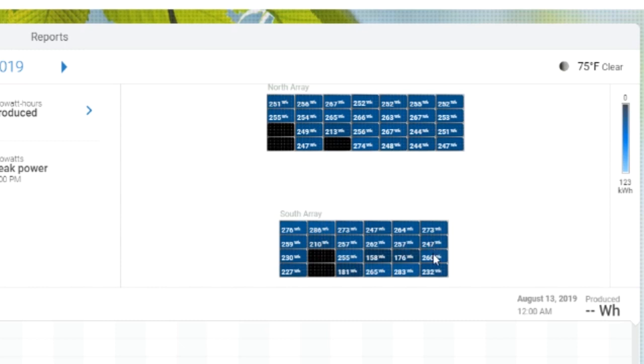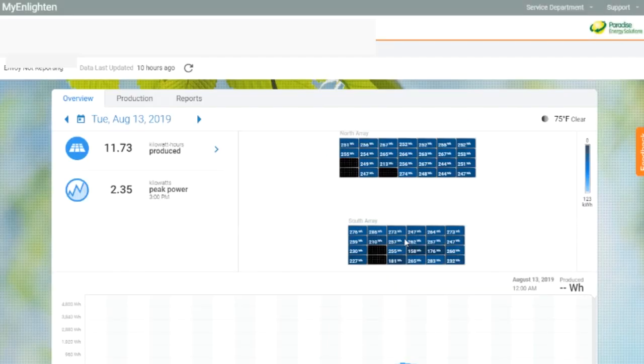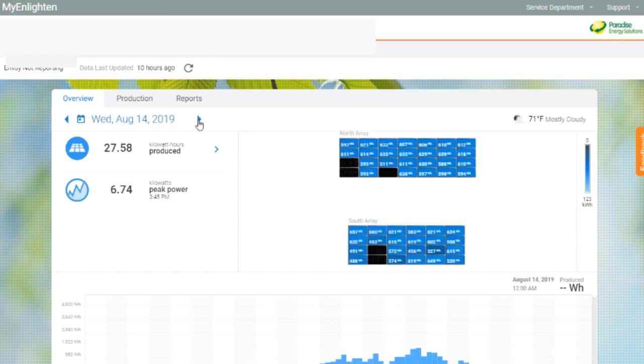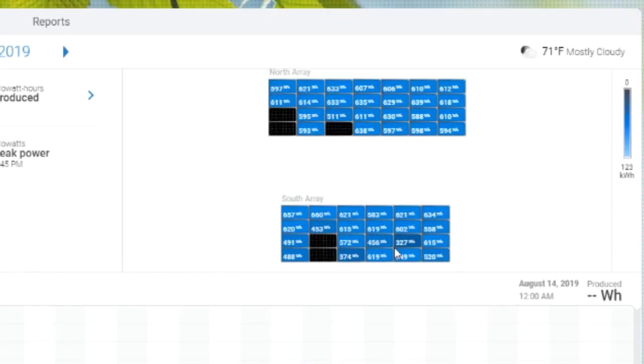So there's a pretty big difference in the amount of production. That tells me that these inverters are probably starting to fail. Let's jump around a few days. This is back on August 13th. Let's jump up to the next day, August 14th. And we're still seeing the same thing. It looks like there was more sunshine on this day.